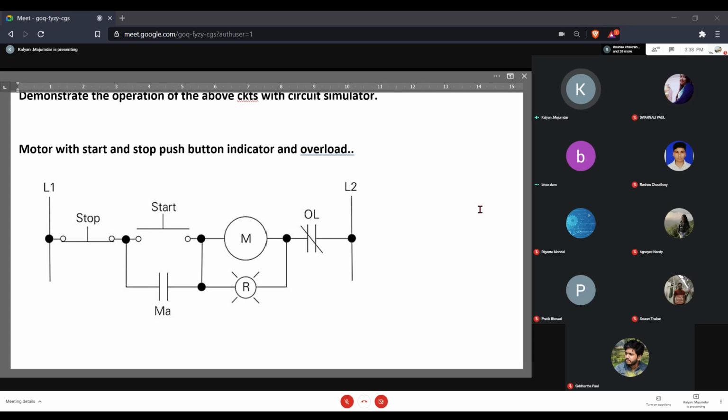মোটরকে স্টার্ট করার জন্য আমার কি আছে, একটা স্টার্ট পুশ বাটন আছে, এটা রিমেম্বার, ইটস আ পুশ বাটন, মোমেন্টারি সুইচ বাট নর্মালি ওপেন। একটা স্টপ পুশ বাটন আছে, আবার মোমেন্টারি সুইচ বা পুশ বাটন বাট নর্মালি ক্লোজড। কি কাজ হবে সেটা নাম থেকে বুঝতেই পারছো, স্টার্টটা আমি যদি মোমেন্টারি প্রেস করি মোটরটা শুরু হয়ে যাবে, আর স্টপটাকে যদি আমি মোমেন্টারি প্রেস করি তো মোটরটা স্টপ হবে। আচ্ছা, তার সঙ্গে এখানে একটা ইন্ডিকেটর ল্যাম্প দেওয়া আছে, মানে মোটরটা চললে সেই স্ট্যাটাসটা কোথাও দেখানো হবে আর কি। আচ্ছা, ওএলটা কি?